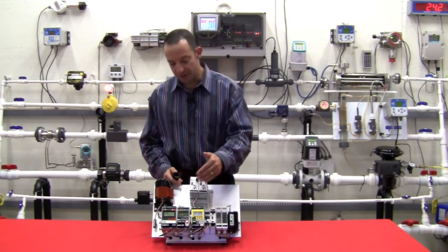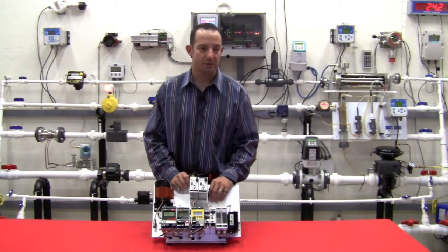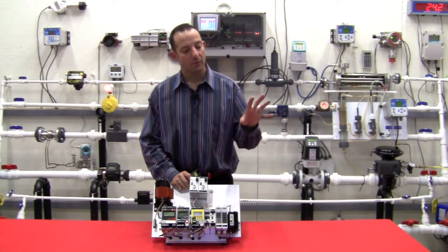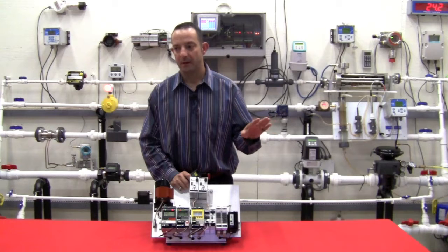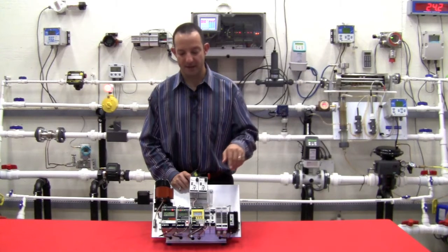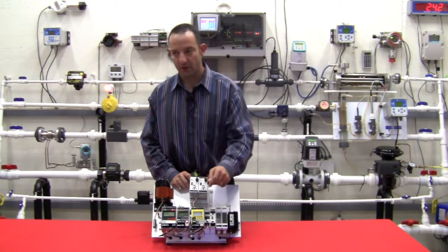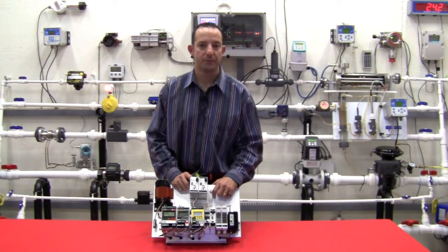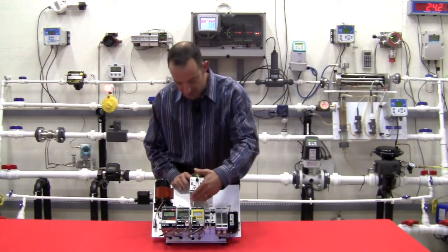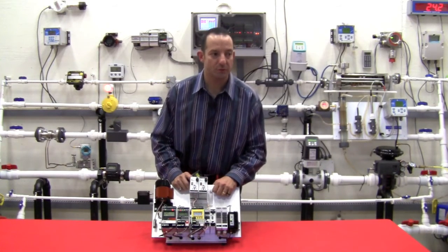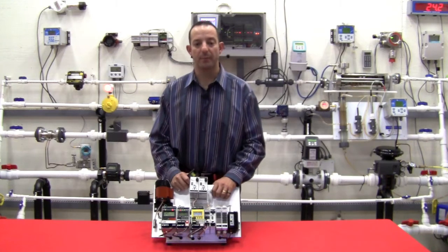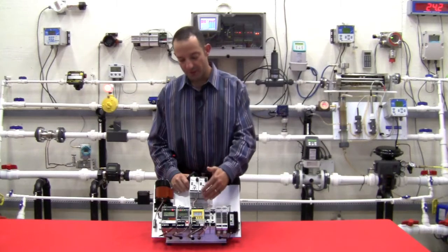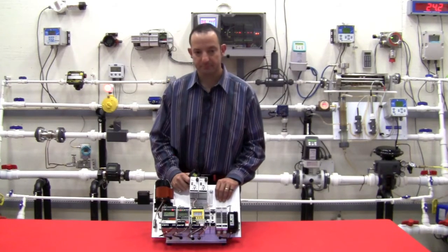What this means is that you can install these alarm trip modules directly in MCC or motor control center buckets with contactors right next to them, and the switching on and off of that contactor won't cause a false trip of the alarm module because of the electromagnetic interference. You can also use a walkie-talkie in the vicinity of the alarm trip, and you won't scramble the circuitry or cause a false trip. Again, it's peace of mind, and it gives you more options as to where you can put these devices in the plant.